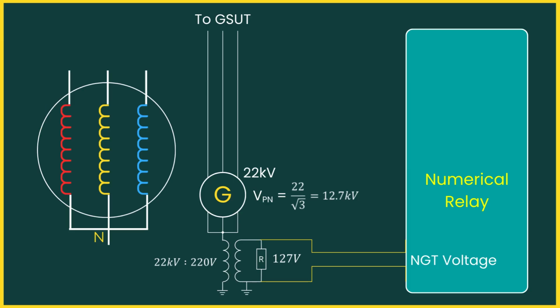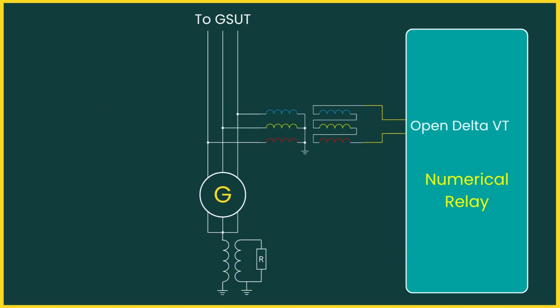A fault located 5% away from the neutral will generate approximately 6.35 volts at the NGT secondary. To ensure 95% winding coverage, the relay pickup is set around 6 volts, so that any fault beyond the first 5% near the neutral is detected reliably. The NGT method is simple, reliable, and provides direct measurement at the generator neutral. Next, the open delta VT method measures the same neutral displacement, but through phase VTs.